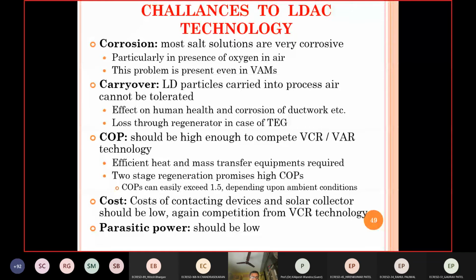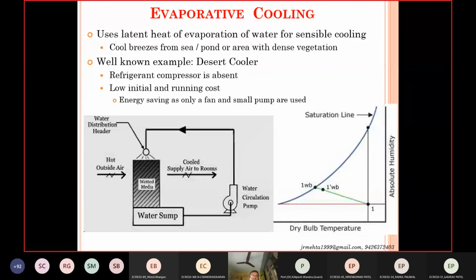And when you are using these thermally fired systems, the parasitic power consumption, the power consumption of components like pumps and fans, should be very low. So you have to adopt that kind of components, fans and pumps, so that the parasitic power consumption is very low. Otherwise, your purpose will be defeated. Okay. Other possible options that can be and should be considered for air conditioning, one of them is going for evaporative cooling. Right?